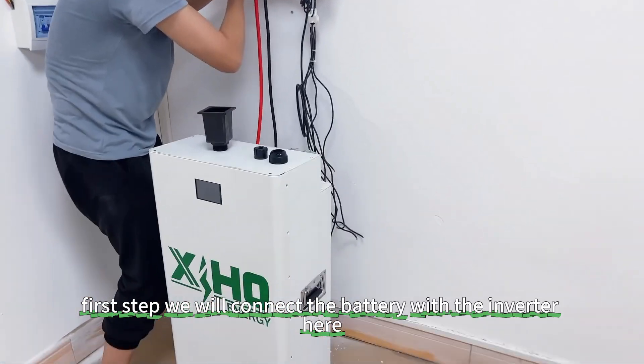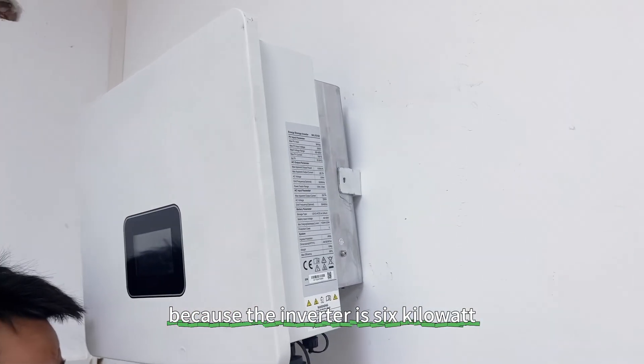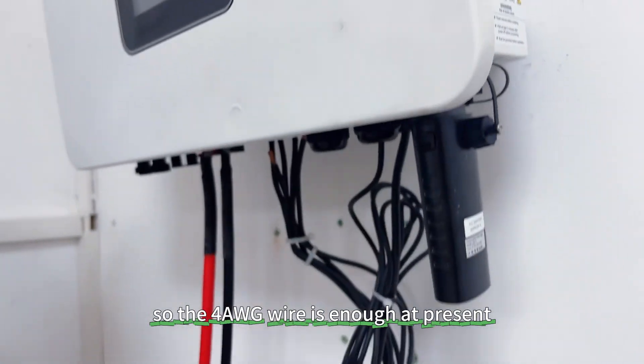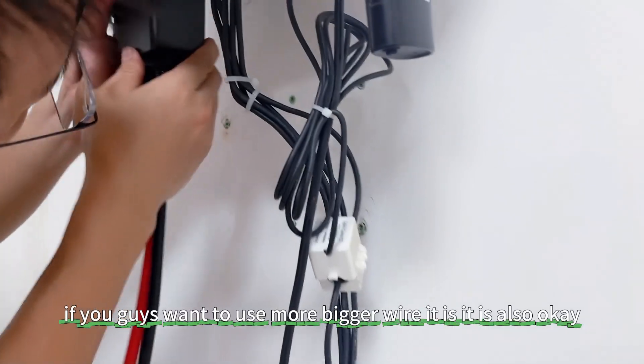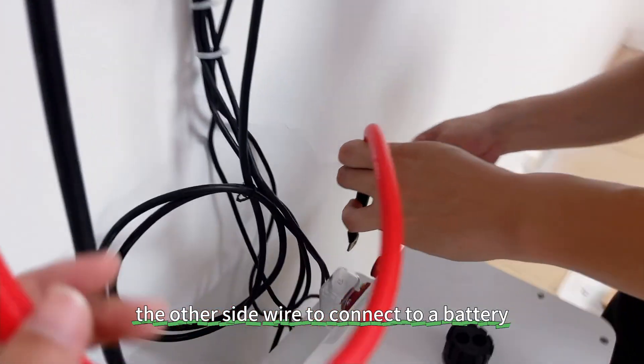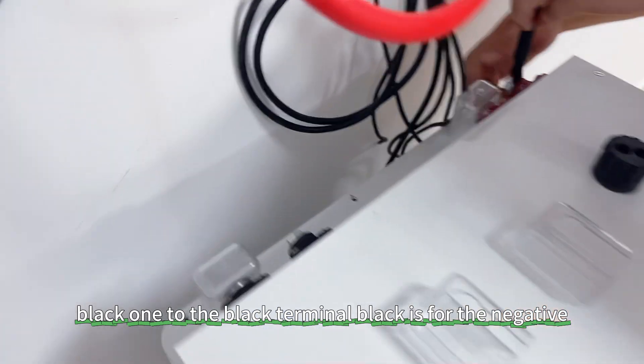Okay, first step: we will connect the battery with the inverter. Here we use two wires. Each of the wires is 4AWG, because the inverter is 6kW and the current is 122 amperes for the charge and discharge current. So the 4AWG wire is enough at present. If you want to use a bigger wire, it is also okay. The other side of the wire connects to the battery — the red one to the red terminal and the black one to the black terminal.